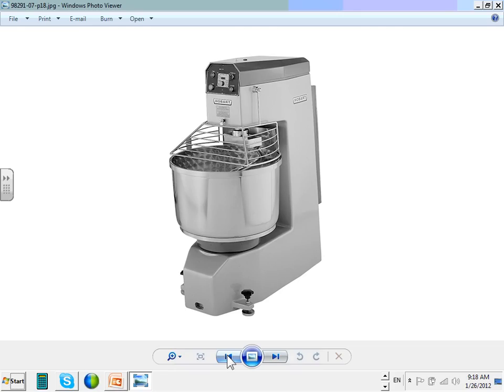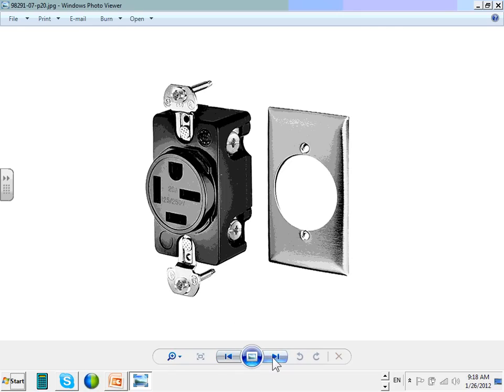you have a lot of appliances there, 3-phase and single-phase appliances. These are where you have to have a disconnect. But most of the appliances, or a lot of appliances, are plugged-in appliances, guys, and the plug itself acts as your disconnect means. So if you go down to our cafeteria at Dunwoody, you're going to find a lot of these fryers and all this stuff. They're all plugged in, single phase or 3-phase. And if you are to work on these machines and the control system is right on the appliance, and if you want to work on them, unplug them, take them, work on them. Unlike an air handling unit where you don't unplug an air handling unit or rooftop units or chiller or boiler, electrical boiler.